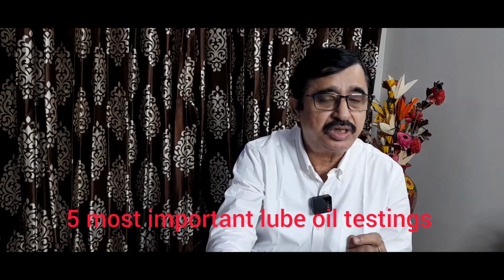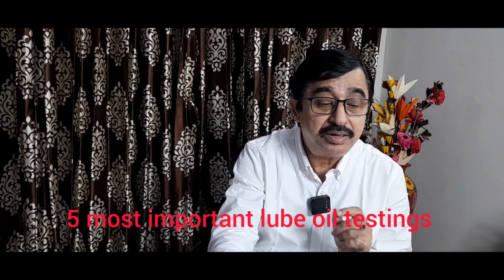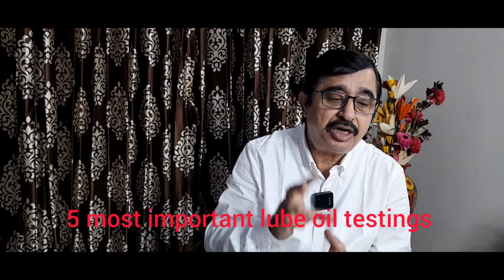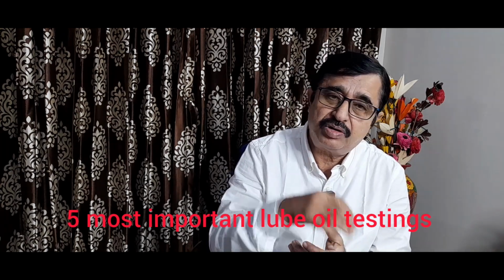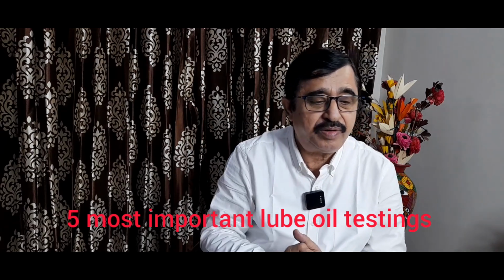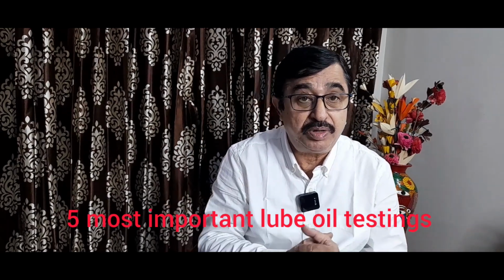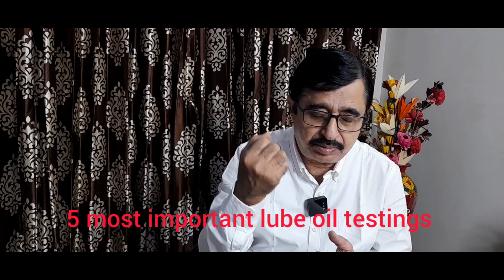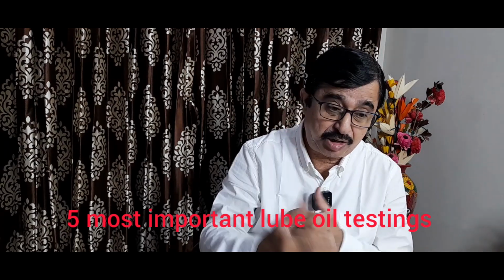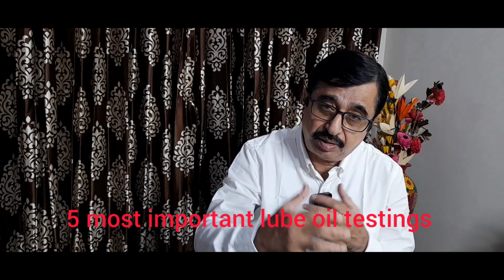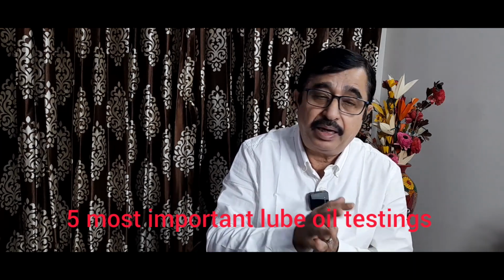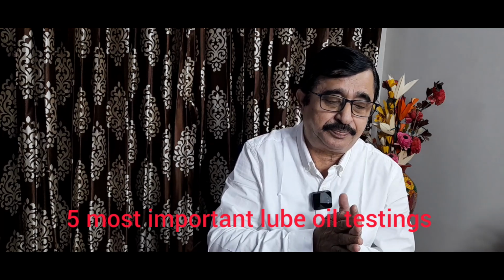Now, regular oxidation testing alerts you to the oil's condition, ensuring timely replacement or decontamination of the oil if it crosses the limit value. This analysis also helps to prevent varnish formation. Varnish is a very dangerous thing in the lubricating oil system and the rotating parts, and it produces a coating on the surfaces and disrupts the smooth operation of the turbine.